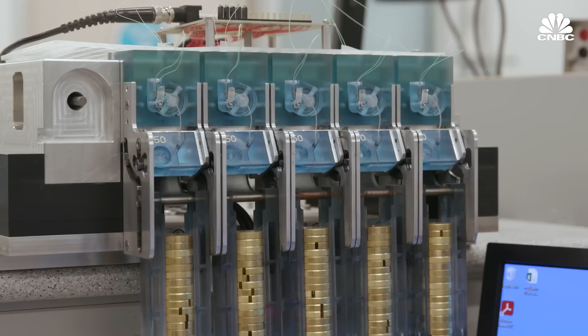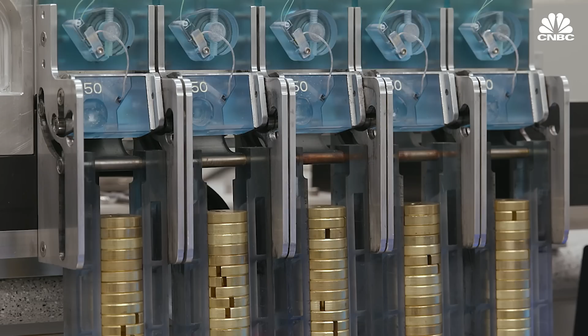Another test gauges the durability of the device's interior components. Sometimes people get a little careless about ripping them out of their ear, and so we want to ensure that this very delicate structure, there's actually 6 little wires that are inside this tube. If they get frayed or kinked, it will stop functioning. The ear is a hostile work environment. It's exposed to the elements in real-world environments where people are perspiring, they're getting rained on, they're sometimes forgetting and wearing their hearing aids when they step in the shower.